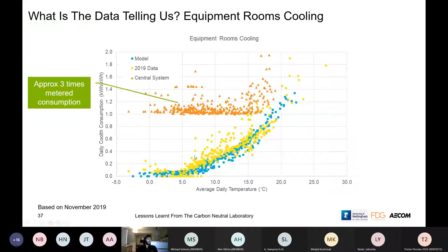But to compare, the orange triangles are our estimation of how much cooling energy we would be using if we had a central system. So we were having to heat and cool the air at that central air handling unit and then provide the cooling in the space. And you can see that obviously there's no free cooling, so we're getting a lot more cooling consumption. Overall, on an annualized basis, that would have been 3 times the cooling demand that we have for our rooms with the local ventilation system. So that's a big saving.